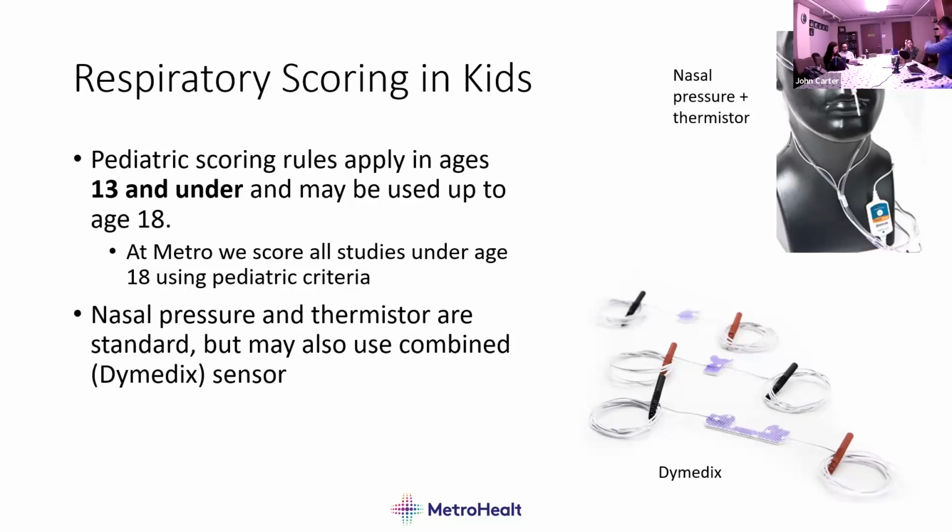So it's going to drop off very quickly. The thermistor signal changes linearly with the temperature change. So what that means is when the airflow drops, the nasal pressure sensor drops off to 0 very quickly, because you're hitting that sort of horizontal asymptote as it's decreasing as the square. Whereas the thermistor is going down linearly, so it's going to take a much greater decrease in airflow before that thermistor hits 0.